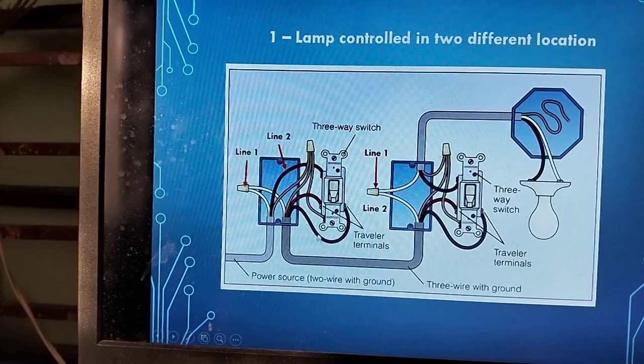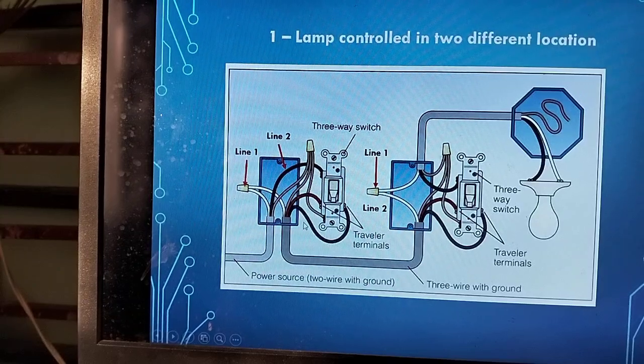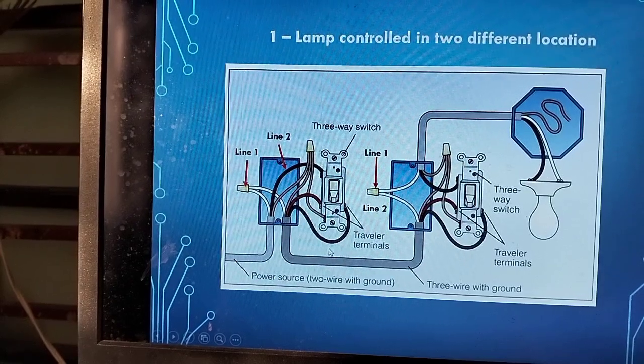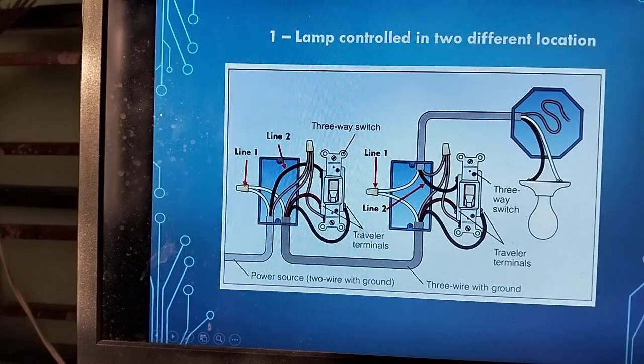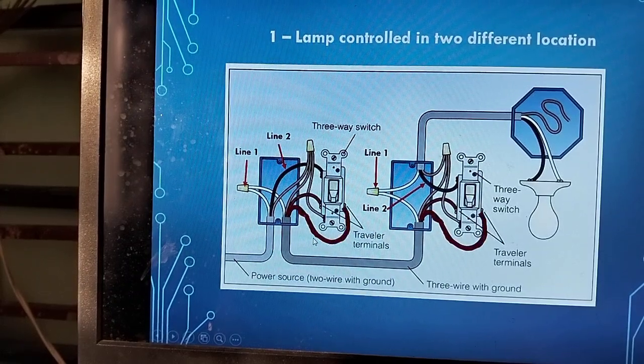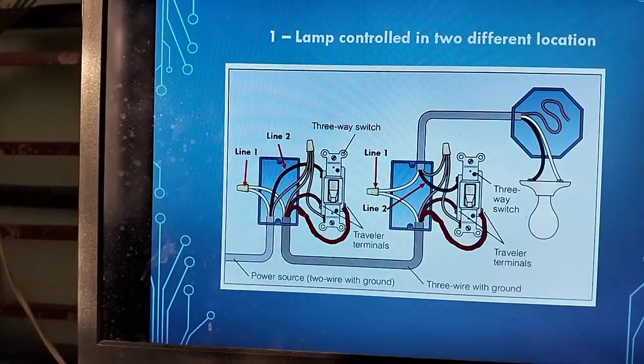The problem now, you don't have enough color-coded electrical wires, like a red wire or black wire. Let's say it is already installed. To make it easier to distinguish, this is a traveler also, because line 2 is black also. To make sure, for quick distinction and troubleshooting, wrap it with electric tape, like that. Because the travelers can be interchanged, no problem. It doesn't cause a short circuit.